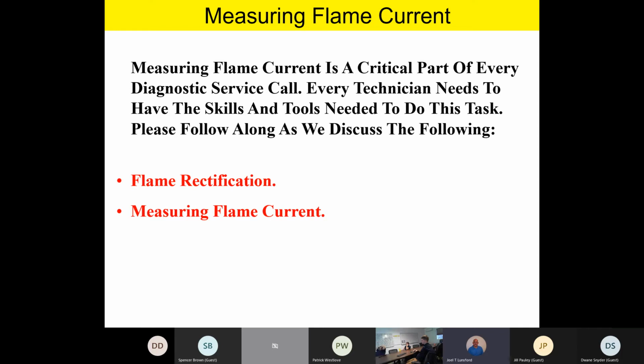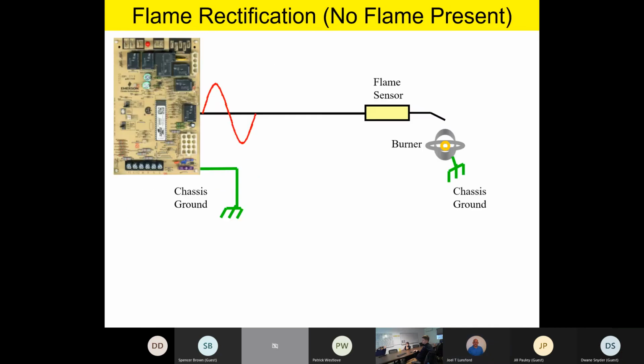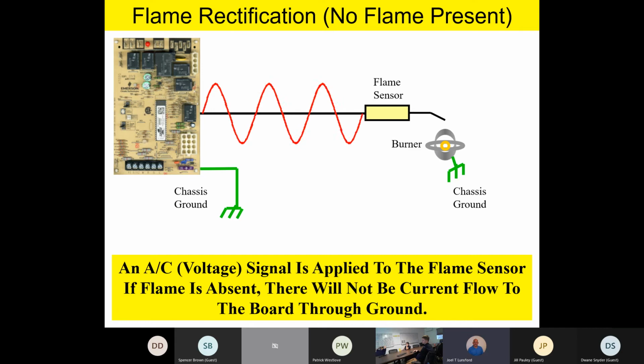And then next year, when you do your clean and check the following year, you can compare to see if it's changed. This is an important skill that every technician needs, to know how to measure flame current. So we're going to talk a little bit about flame rectification and the science behind it, and then how we're actually going to measure flame current on our control board as we wrap up the session and open the floor up for questions and comments. So flame rectification is a pretty simple process. It's quite brilliant, whoever came up with it. But anytime we have power to the board, we have AC voltage going to the flame sensor.